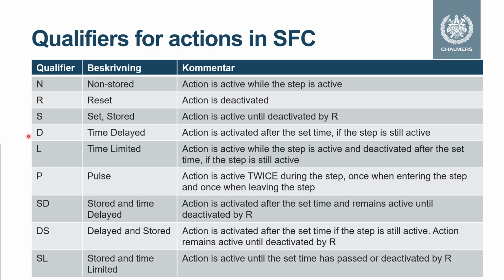We can have a time-delayed activation of the action. If the program is still in the step after the set time, the action will be activated. We can also have a time-limited action. Then the action is activated directly when the program enters the step, and then it will be deactivated after the set time if the program is still in the step, or it will be deactivated when the program leaves the step. The P for pulse, and we have different combinations of time-delayed and stored, and time-limited and stored.